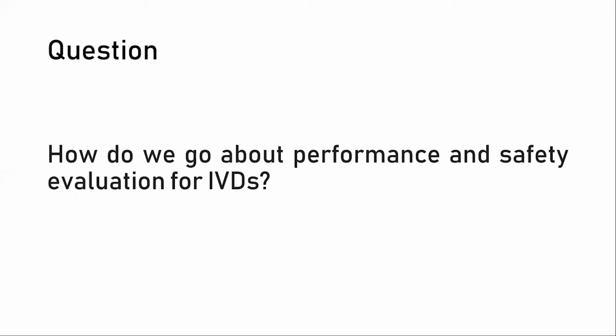So maybe my original performance evaluation was actually done on version 1 of the product, but I had to make a series of changes. We've all had the nightmares of having to change because detergent changes, anti-foam changes, and things like that. But is the data in that original performance evaluation actually still relevant to the product that's on the market today? It may be a different formulation. Therefore, you may actually be presenting data as part of those changes that you've done. And to be honest, sometimes that data is of a better quality for very old assays, because your quality system has evolved and improved over time, and that's data you're much more proud to present than perhaps the original data, because some of these assays can be really quite old.